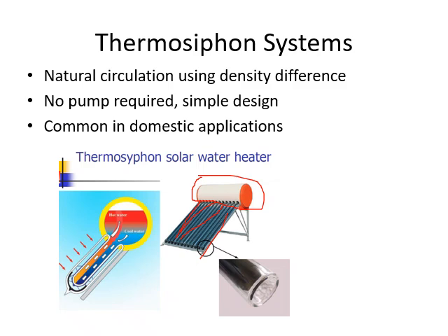So you can see in detail, you know that hot water will always try to travel upward, and the cold water is heavier, so it will naturally go downward. We apply this technique in this thermosiphon system. So from this tank, by gravity, the water will flow downward, right? And why is there this inclination? To absorb an optimized amount of the sunlight coming here, right? That's why we use it as inclined.